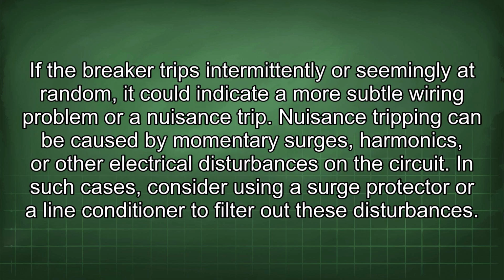If the breaker trips intermittently or seemingly at random, it could indicate a more subtle wiring problem or a nuisance trip. Nuisance tripping can be caused by momentary surges, harmonics, or other electrical disturbances on the circuit. In such cases, consider using a surge protector or a line conditioner to filter out these disturbances.